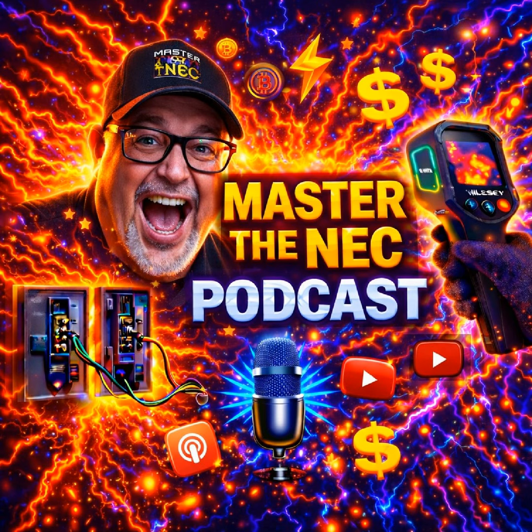If I say a GFCI doesn't require an equipment grounding conductor to perform differential current sensing, somebody on social media is going to take that and shorten it and say, hey, Paul said equipment grounding conductors don't matter if you have a GFCI. That is not what I said. That's not even close. Nothing takes the place of an effective low impedance ground fault current path, the EGC. What we're saying is that the GFCI doesn't require an equipment grounding conductor itself to perform its differential current sensing function. That's all we're saying.